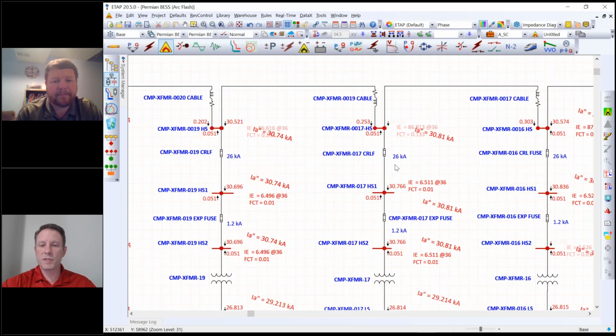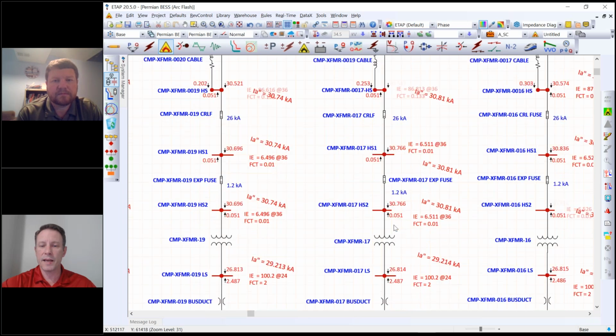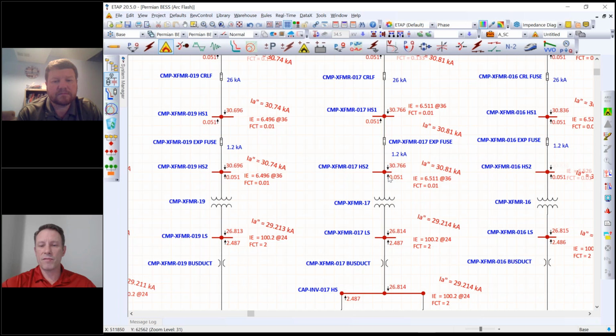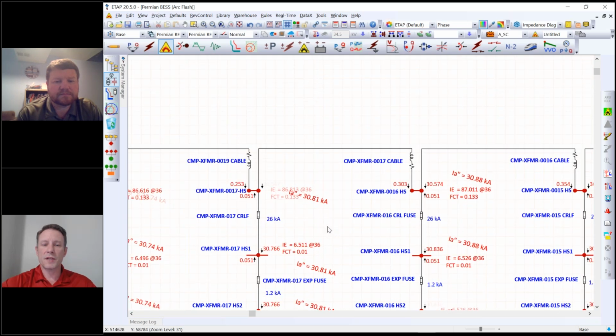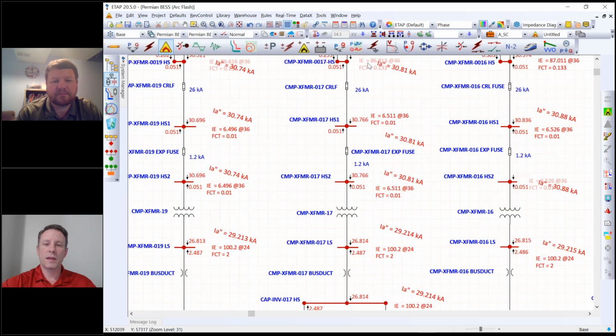But there's a fuse here and a fuse here. These are both the transformer fuses on the high side. It's not very bad right here at the high side of the transformer, just because these two fuses will take that down. Whatever protection is up here for the relaying for the utility, that could lower this 86 cals too, even if it is a little inflated from the Lee method.